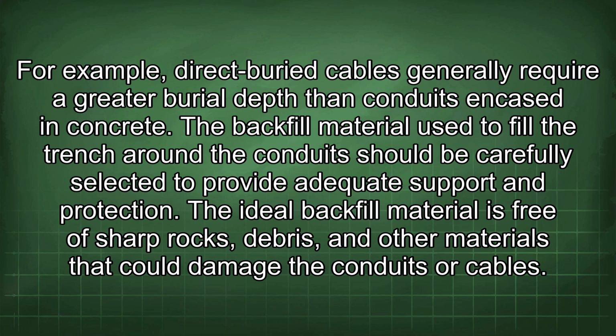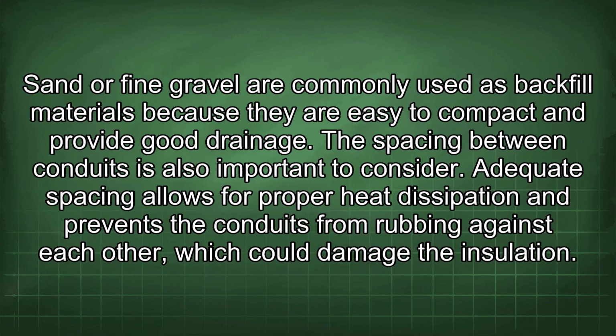The backfill material used to fill the trench around the conduit should be carefully selected to provide adequate support and protection. The ideal backfill material is free of sharp rocks, debris, and other materials that could damage the conduits or cables. Sand or fine gravel are commonly used as backfill materials because they are easy to compact and provide good drainage. The spacing between conduits is also important to consider.